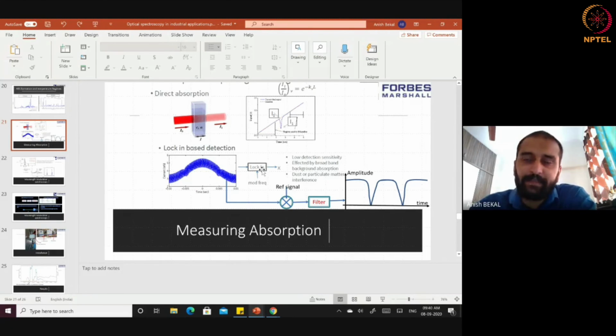They define it as: if you're measuring 100 ppm, and your maximum detection capability is 100 ppm, they put around 90 ppm of gas inside and look at the fluctuation of the gas amplitude in the measurement, and that has to be less than 2% of your full scale reading.